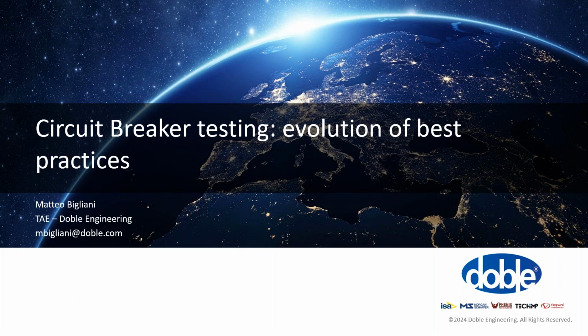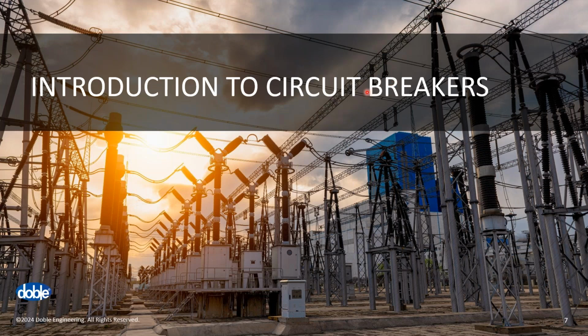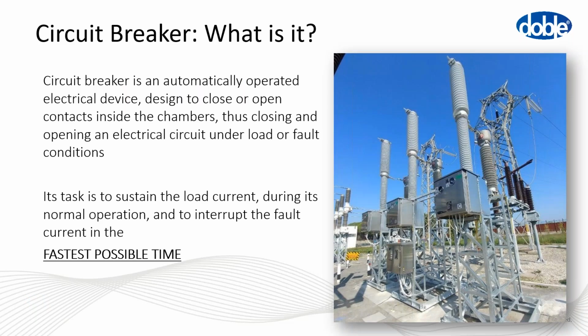So we can start. The first topic is an introduction of the circuit breaker, so how they work and how to test them. Okay, what is a circuit breaker? Basically, it is an automatically operated electrical device. It is designed for 2 main purposes. The first one is to sustain the load current during its normal operation. So if there is no fault in the line and no fault in the circuit, you just have to sustain this current. The second purpose is to interrupt the fault within the fastest possible time. So in case of a fault, it needs to open in a very fast way.